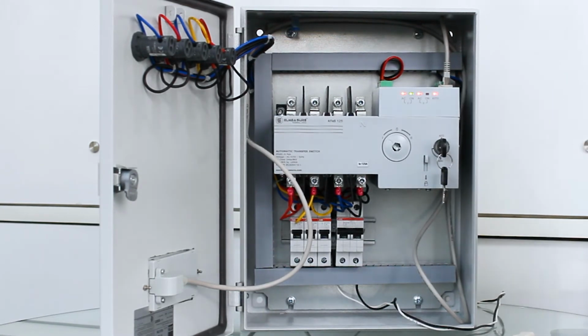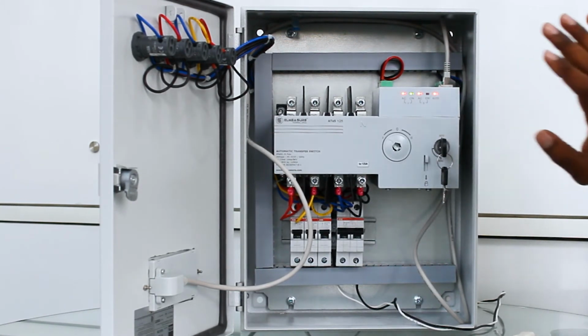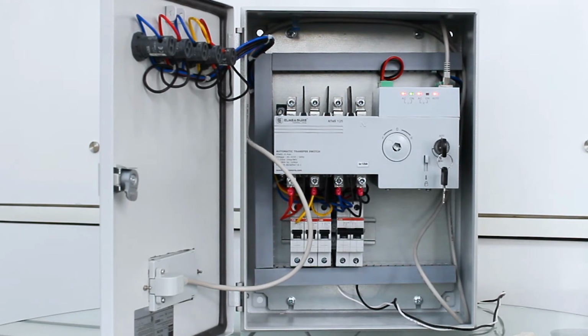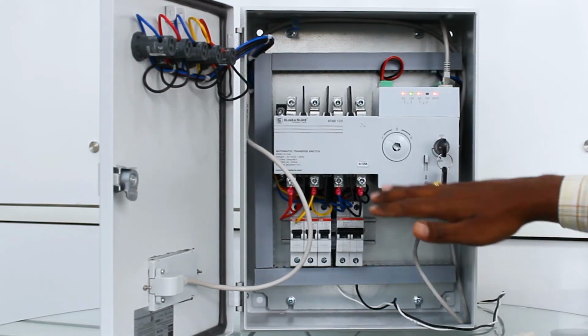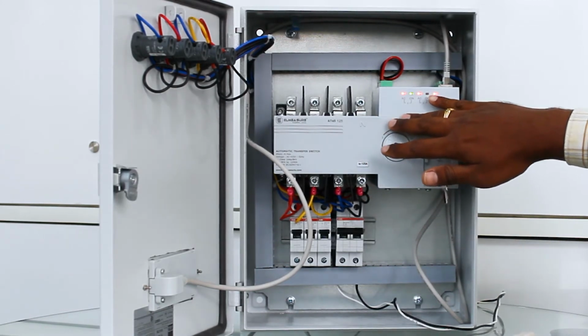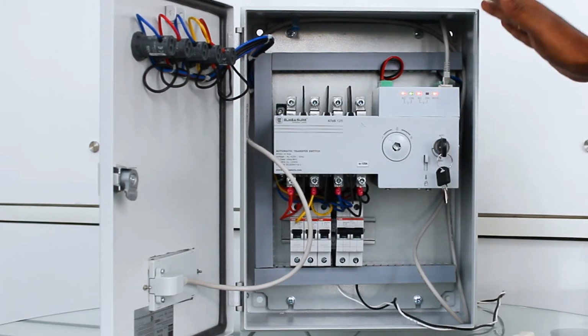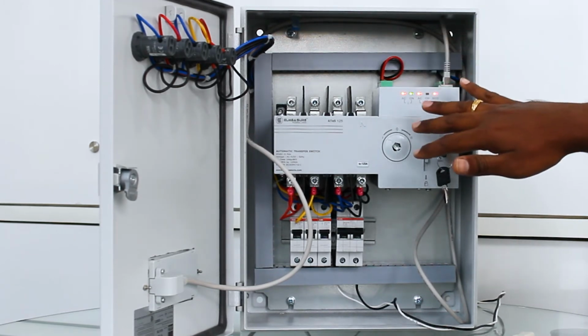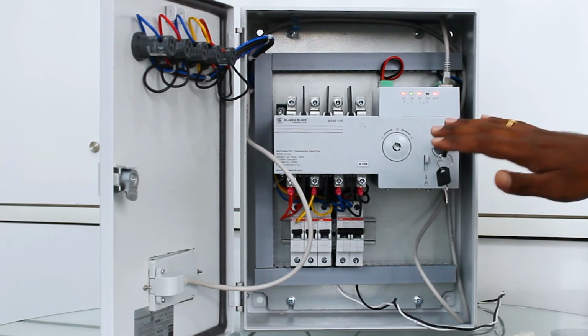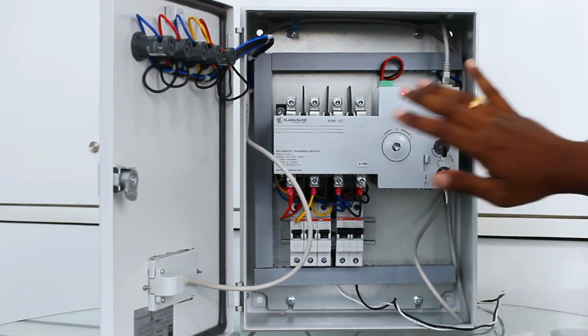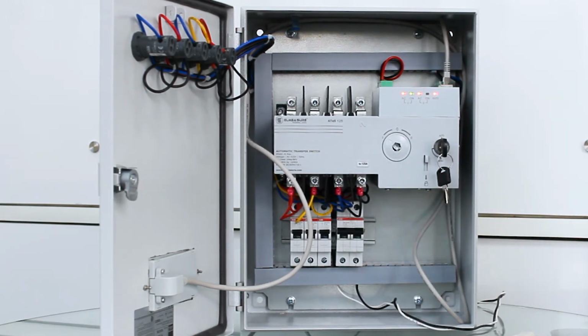In this product we have under voltage protection. If in case of any under voltage or over voltage on the transformer, the ATS will immediately come to trip position and initiate the generator start. Once the generator supply is present and the voltage and frequency are healthy, it will move from transformer to generator side.